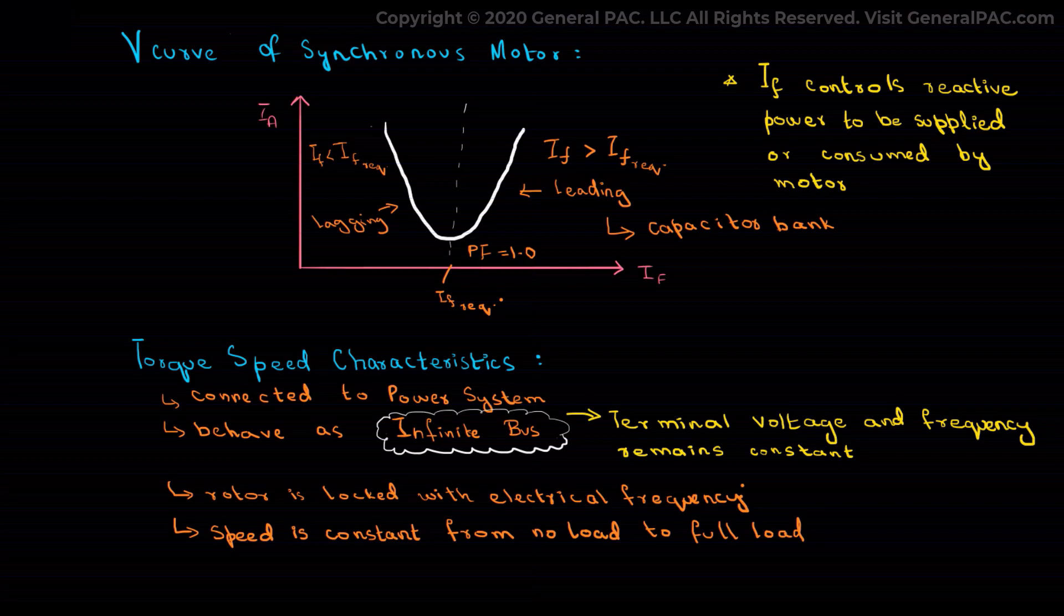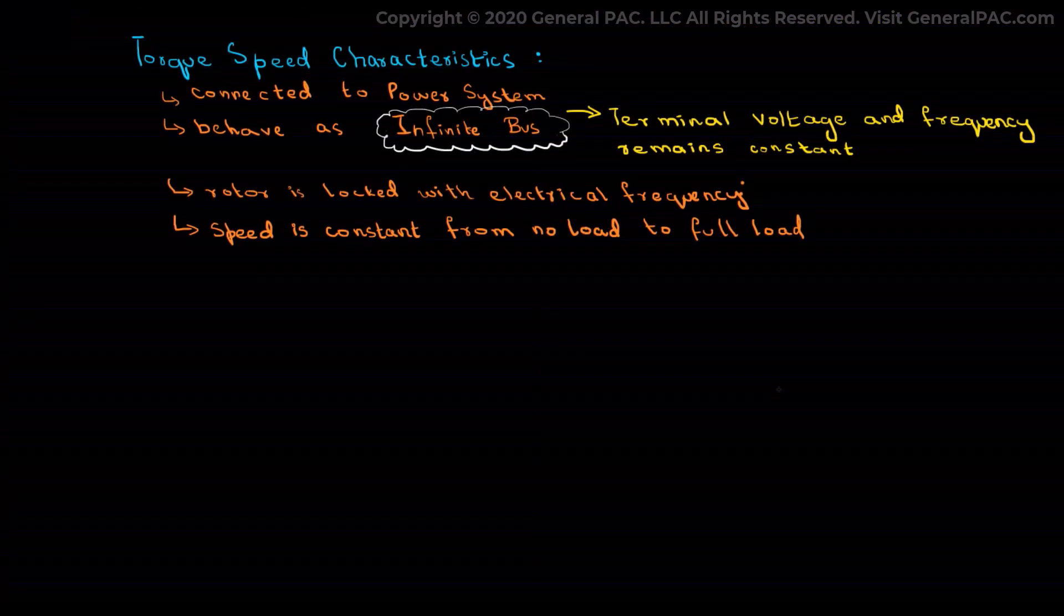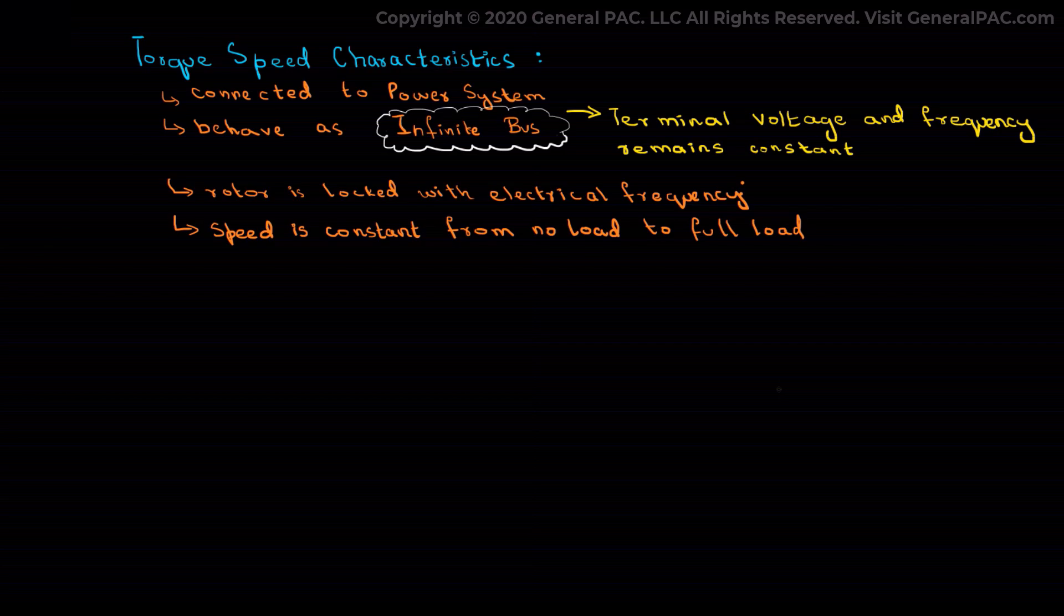Let me repeat this again because I feel like this is a very important point to make here: the speed of the synchronous motor is constant from no load to full load or even the pull-out torque, the maximum torque that the motor can supply. So we can conclude here that the speed regulation of a synchronous motor is essentially zero, as shown in the figure below.